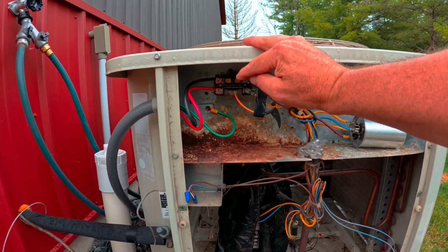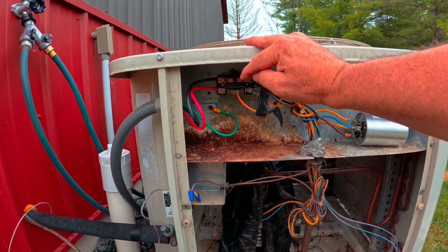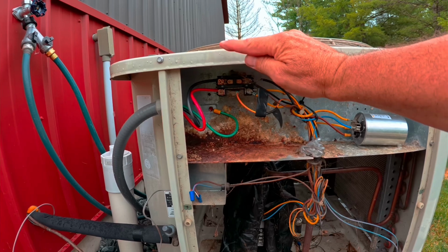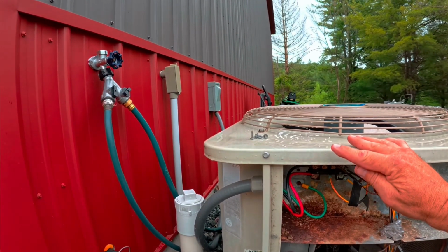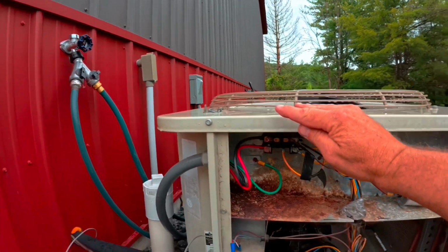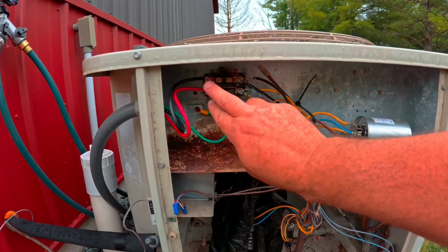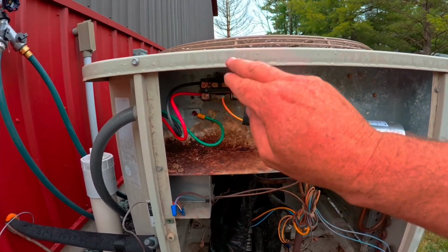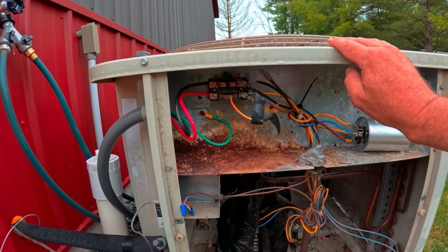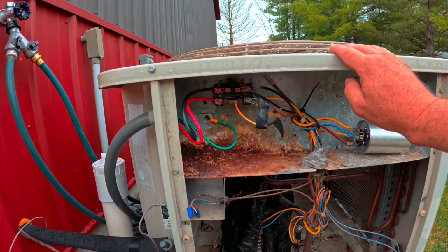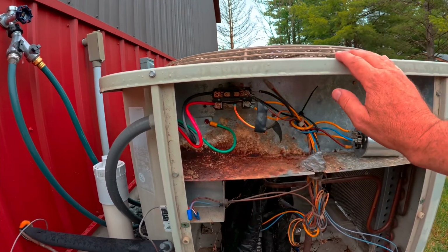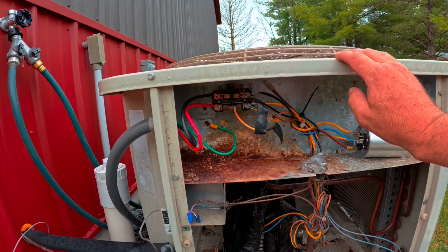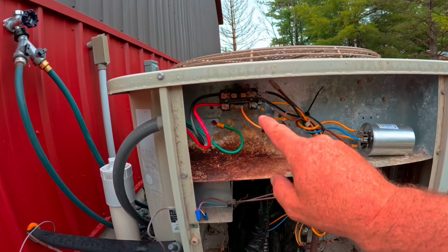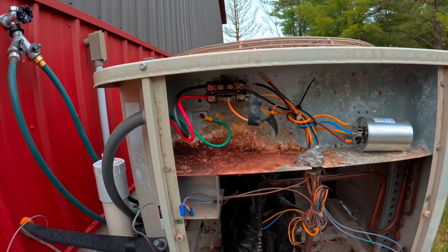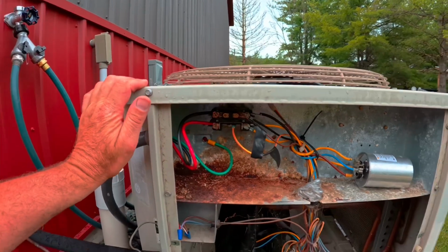If that is the case, which is most common, then you need to shut off your disconnect switch on the wall over there, make sure there's no power going to the unit. Then you need to take your voltmeter, verify that there is no voltage going to that unit anywhere, and then, and only then, can you try to fish him out of there. But if you're going to do it correctly, buy a new contactor, replace it. It is a wear item. It is going to fail.